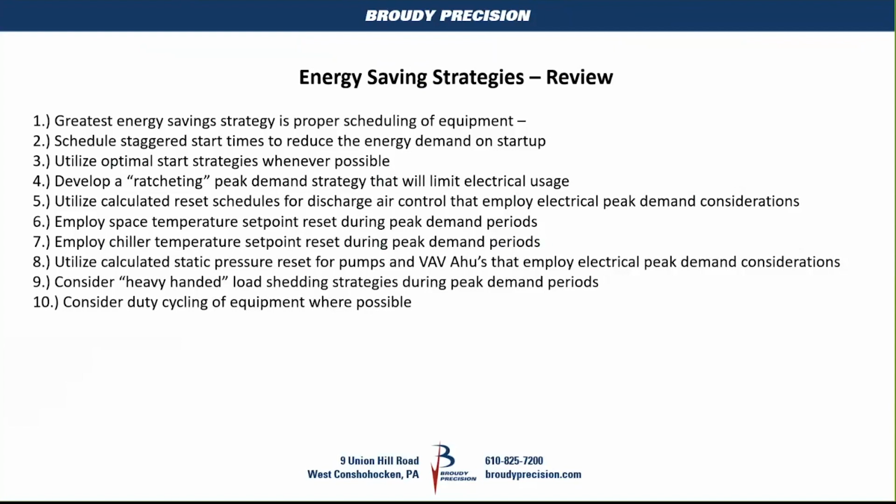In the Honeywell world, our controllers have built-in capabilities to do a staggered start. In the Johnson world, same thing. In CCT programming and in the CIPer and Spyder programming, we have the ability to stagger our starts through a command variable. That will reduce our kW, our energy demand on start. That just makes good sense.